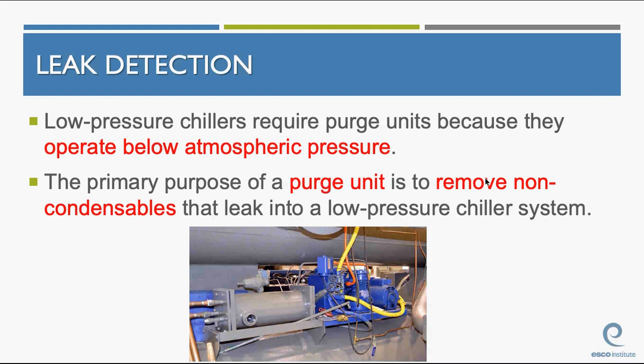A low-pressure chiller requires a purge unit because they operate below atmospheric pressure. The primary purpose of the purge unit is to remove non-condensables that leak into a low-pressure chiller. Again, we have an extra part of the system on a low-pressure chiller. It's called a purge unit. It has one purpose, to remove the non-condensables that leak into a low-pressure chiller. And what you're looking at here on the screen is a purge unit.